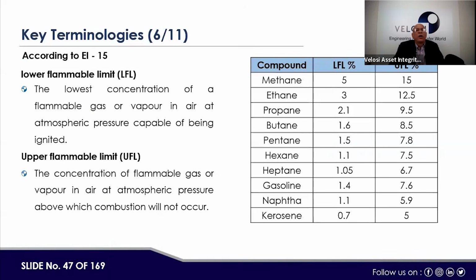Similarly, according to EI-15 or IP-15, there is LFL and UFL. LFL means the lowest concentration of flammable gas or vapor in air at atmospheric pressure capable of being ignited. And UFL is the concentration of flammable gas or vapor in air at atmospheric pressure above which combustion will not occur because the oxygen concentration would be lower. For methane it is 5%, ethane 3%, propane 2.1% in the air, butane 1.6%, pentane 1.5%, hexane 1.1%, heptane 1.05%, gasoline 1.4%, naphtha 1.1%, kerosene 0.7%. A higher range is also given where ignition will not take place.